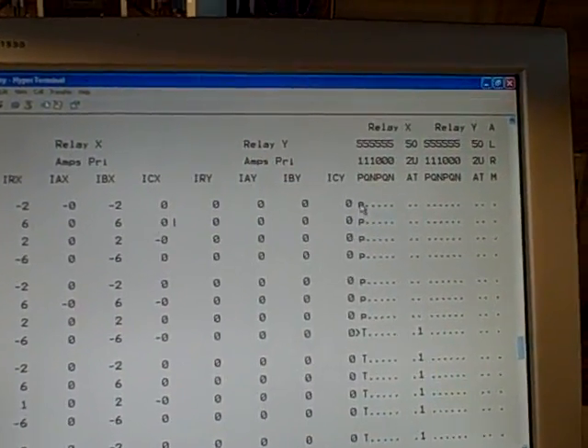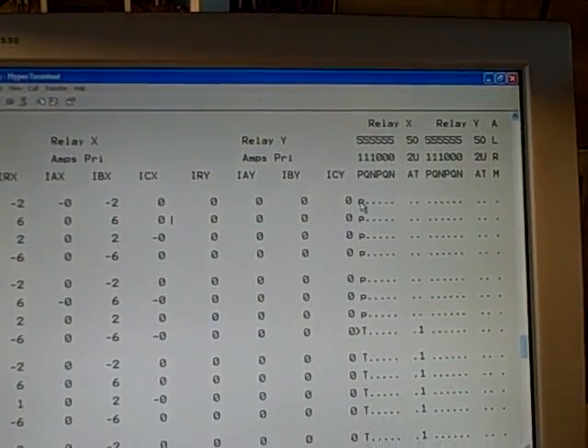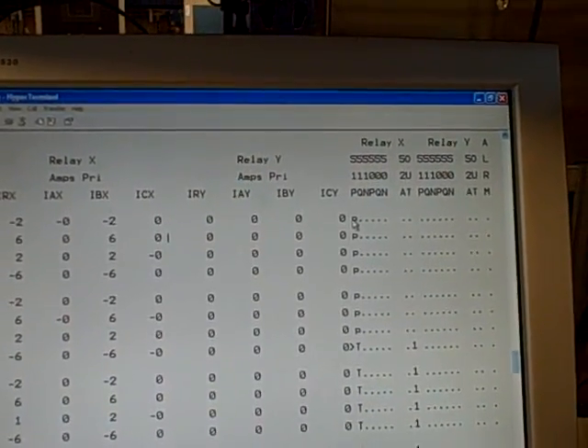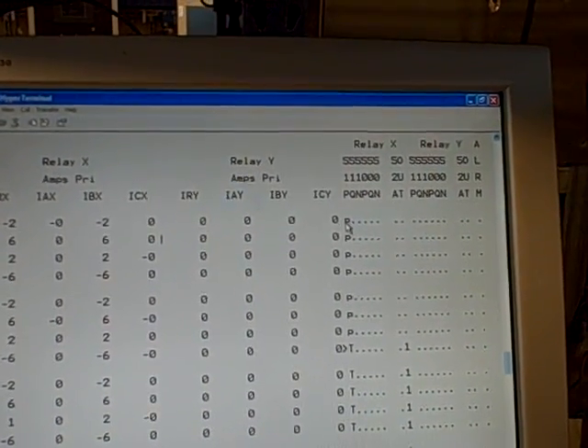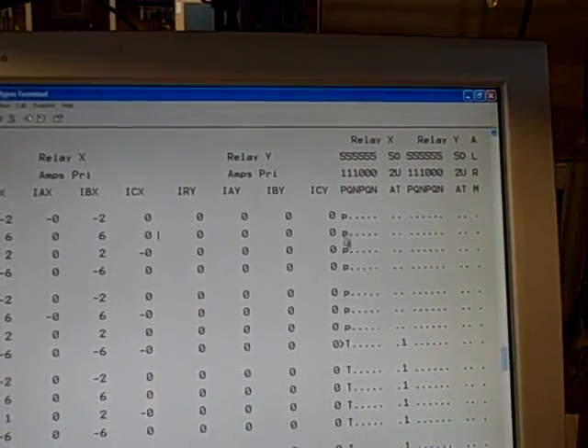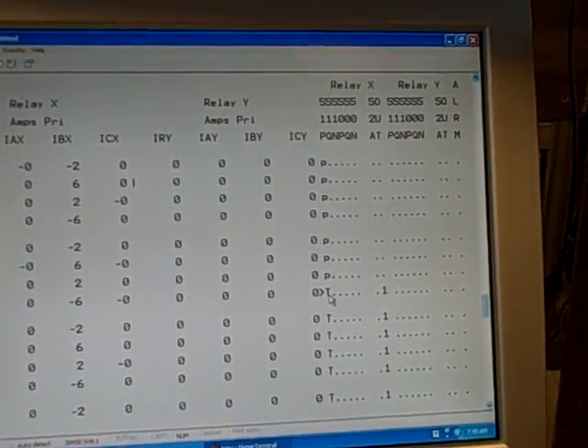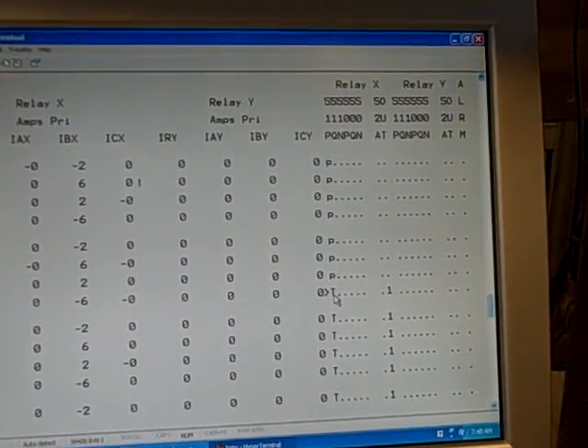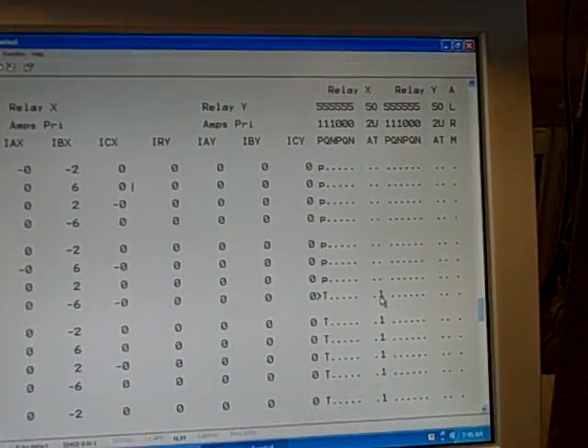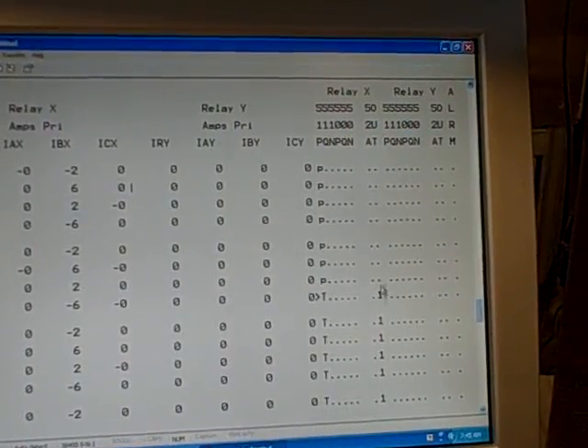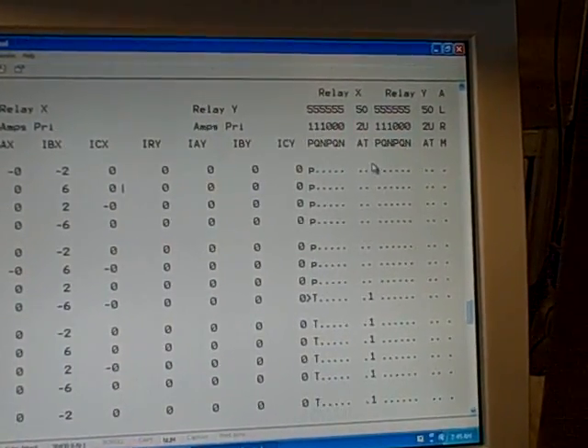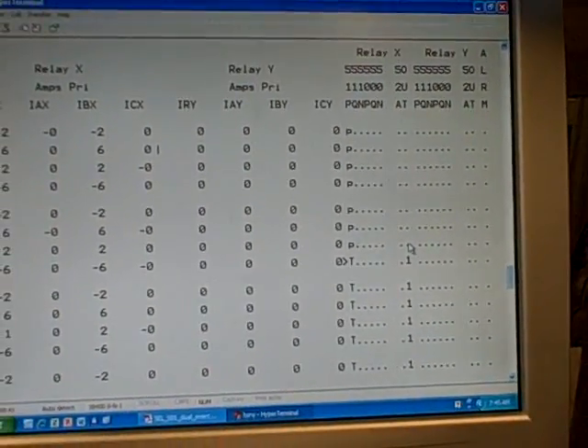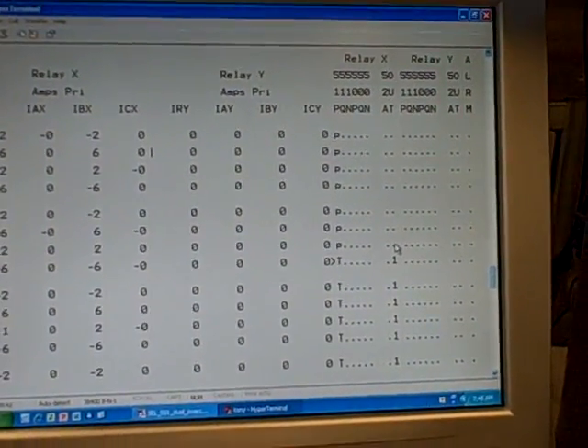Again, the lowercase p tells me that it has picked up under this phase over current 51P element. The capital letter T tells us when it has actually initiated a trip, and we see that with a number one under the output column where it's asserting the output contact to actually trip the relay.